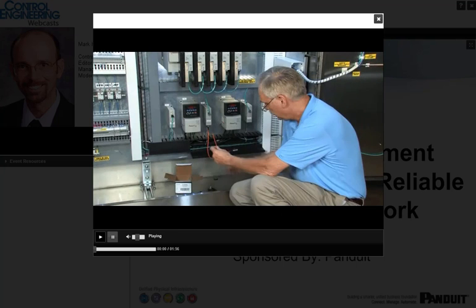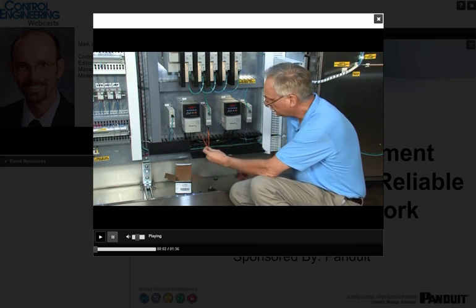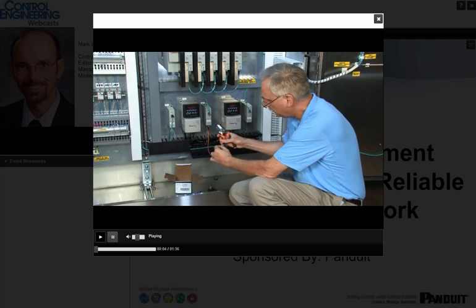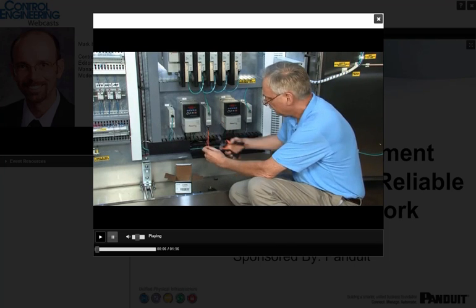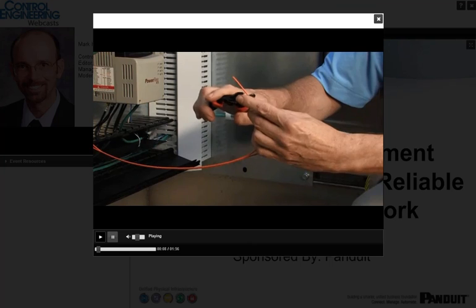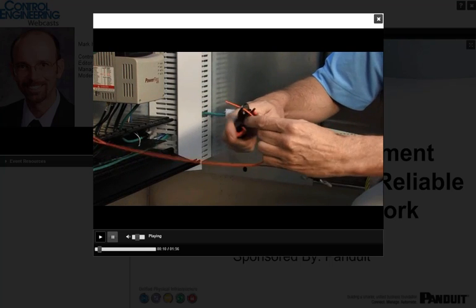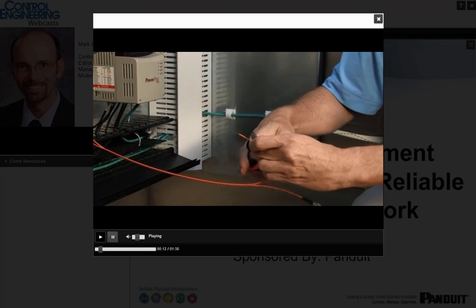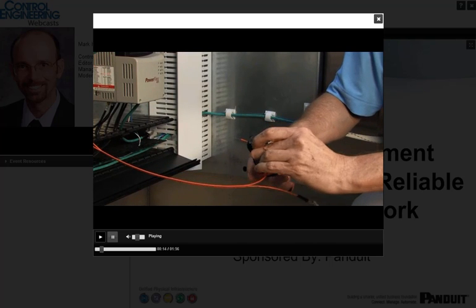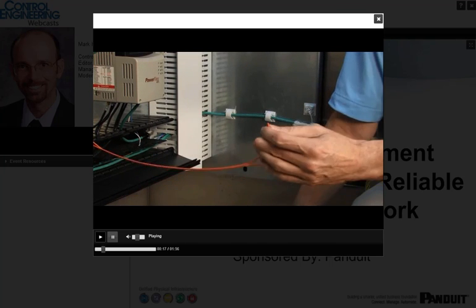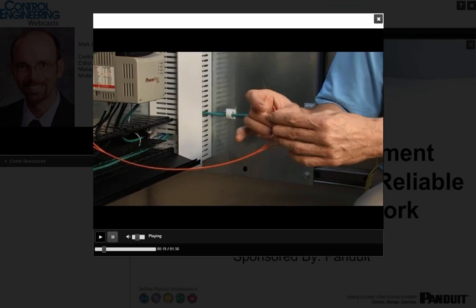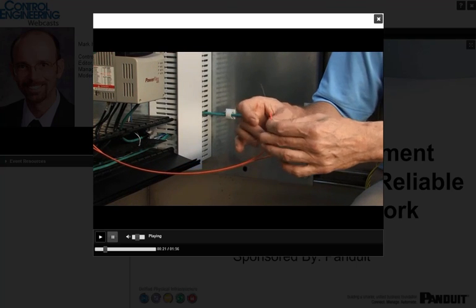Today we're going to do a field termination with the Panduit LC PCF connector. I pre-terminated one end and it's plugged into the ETAP. I'm going to take my strip tool. I've got a gauge mark marked on the jacket itself. I'm going to take off the jacket in two passes. So what I've done here is remove the jacket material from the PCF cable. It's a zip style cable.